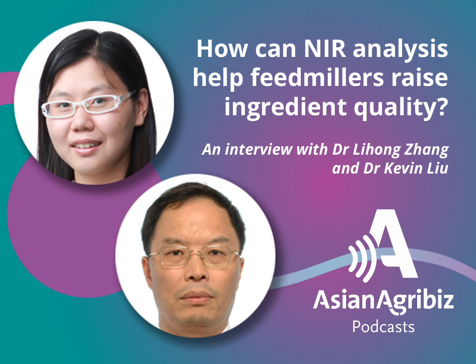So the sample representativeness and the wet chemistry methods will determine the quality and the reliability of the NIR calibration and prediction. Finally, monitoring the performance of a calibration and enrichment over time is also important as part of the NIR platform process. And during NIR analysis monitoring, if NIR results continue to fall outside the control limit or exhibit many larger H values or MD values, it is necessary to recalibrate with a new sample population.